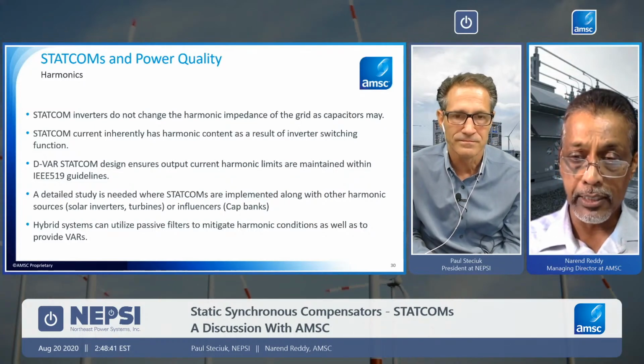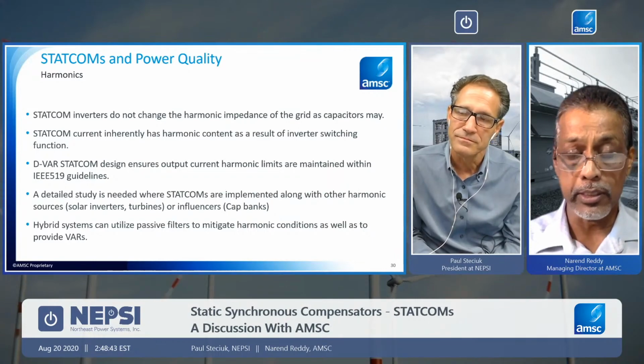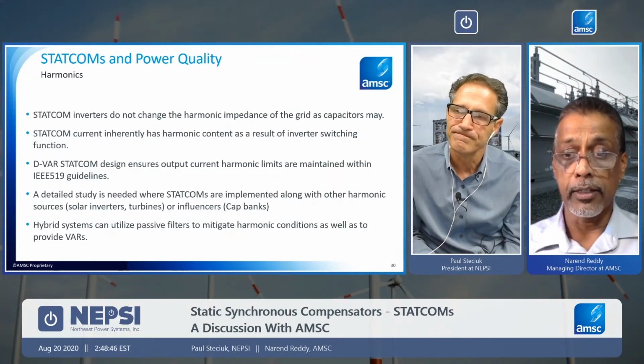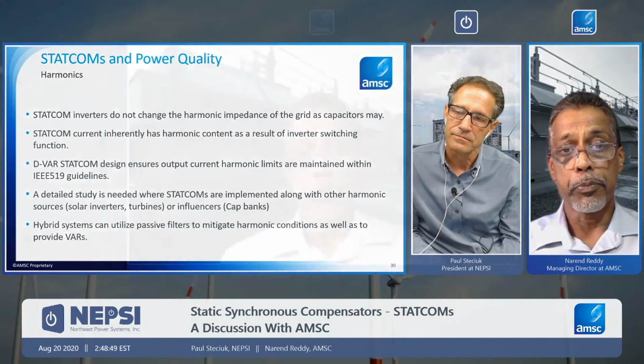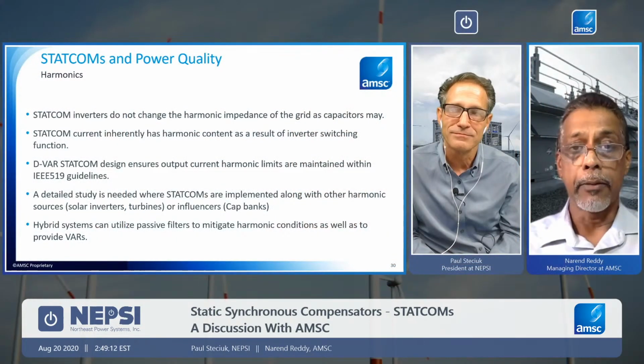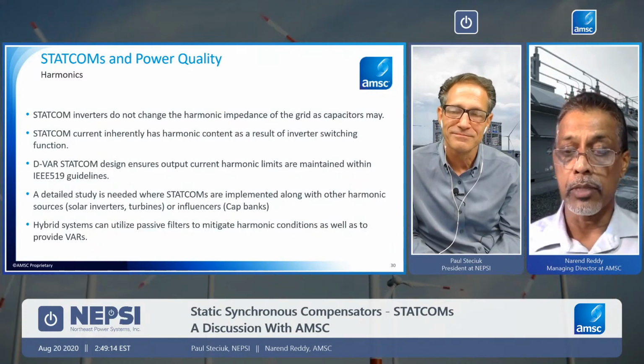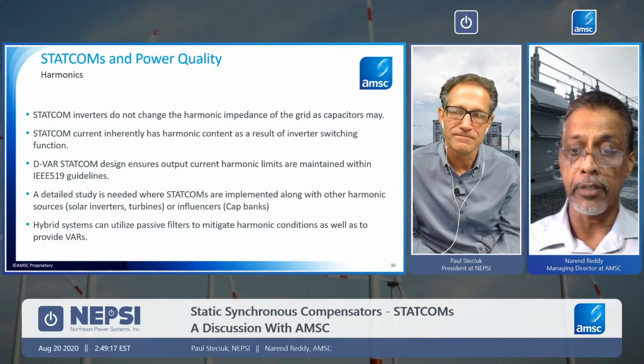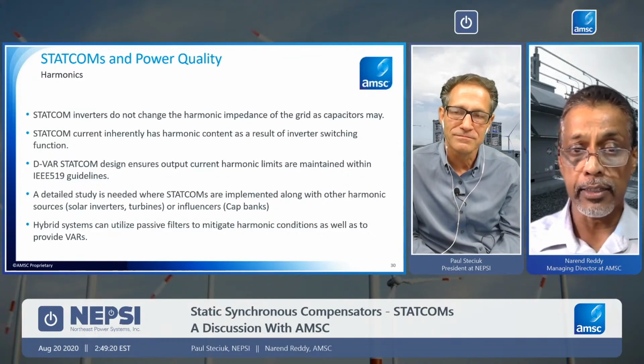there is switching of these IGBTs at a very high frequency, at 4.5 kilohertz per inverter. That's a pretty high frequency. But there are also techniques that we use internally because we don't have a single inverter, we have multiple inverters. And so effectively, at a system level, there are ways that we can increase that effective switching frequency much higher. Now having said that, those harmonics are really managed or contained within the STATCOM unit.